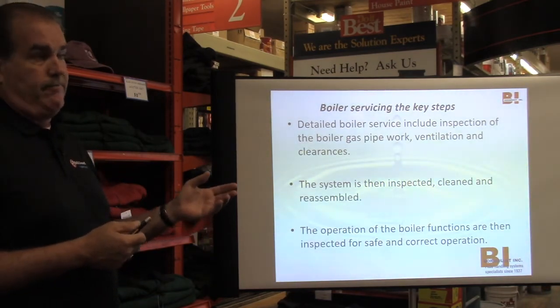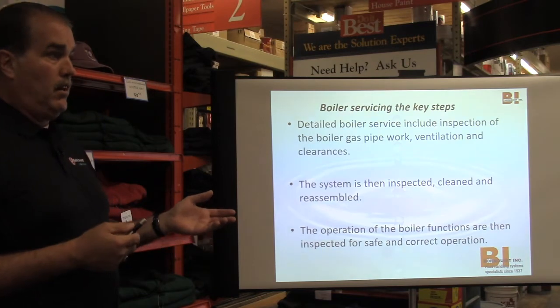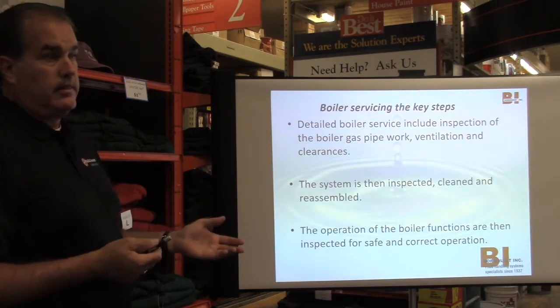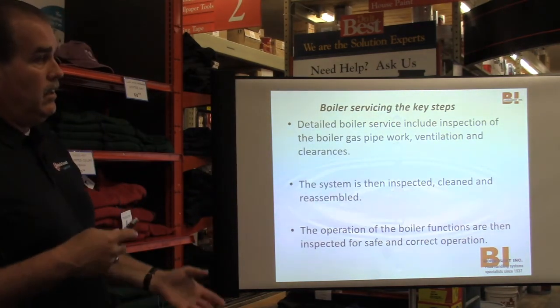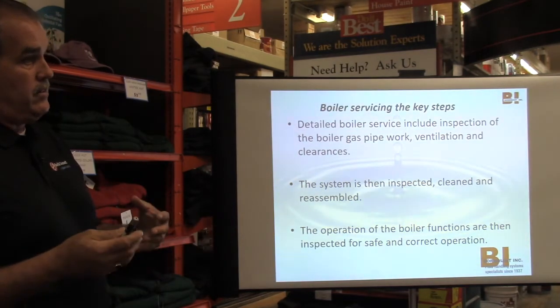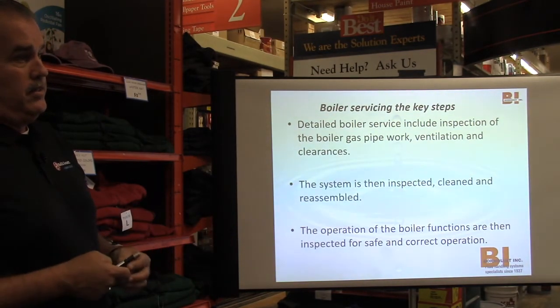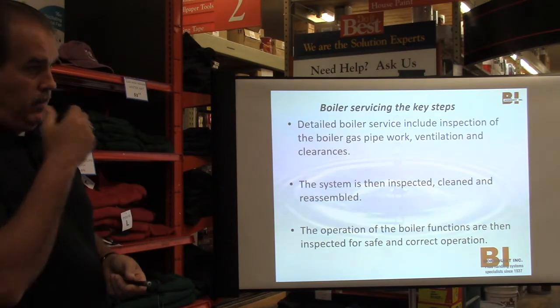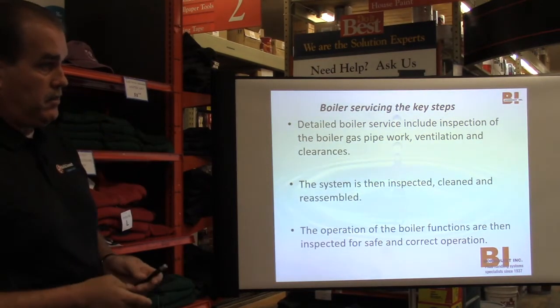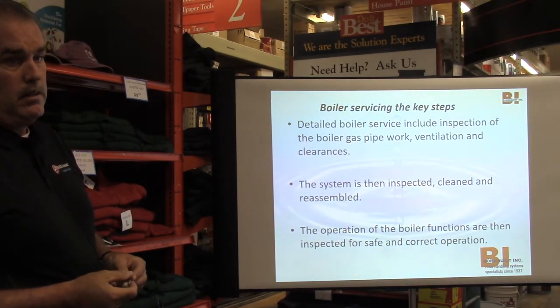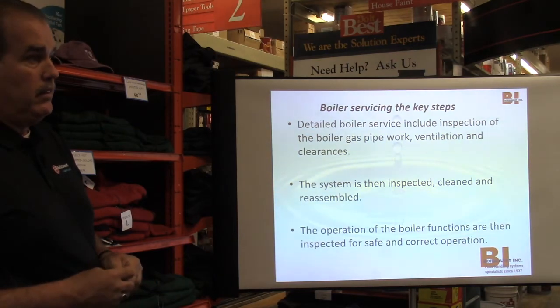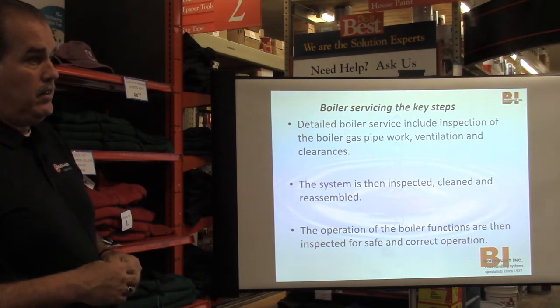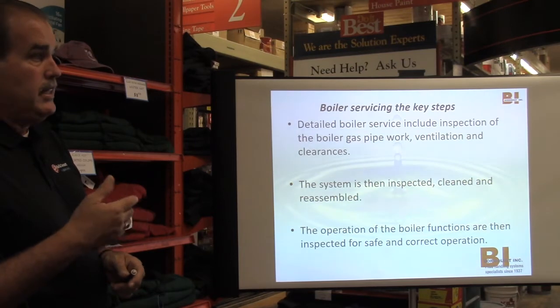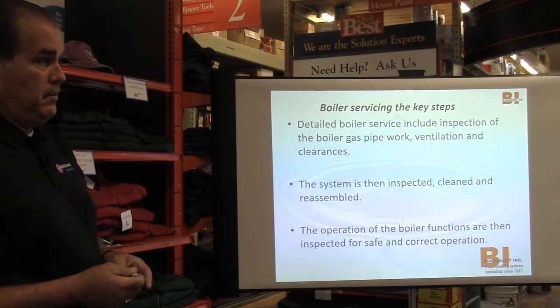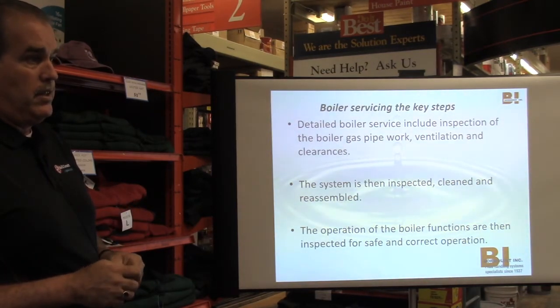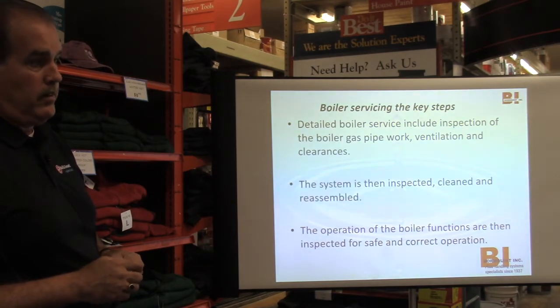I've seen them as low as 1,000, but even so, it's 1,000. That's not cheap. So they should have that. Now that's the reason I bring that up: if you got somebody who is going to service your boiler, you might want to ask them, what are you going to do? Ask them, what are you paying for? You have a right to know. And one thing you want to make sure he's going to do is, in the end, check combustion and verify that the combustion is within the parameters of the boilermaker.